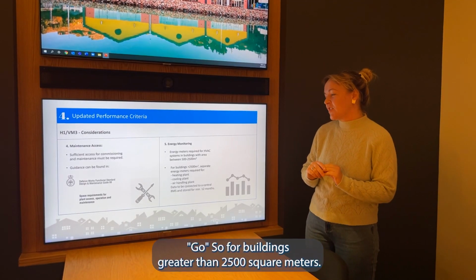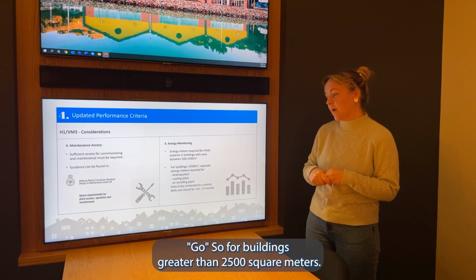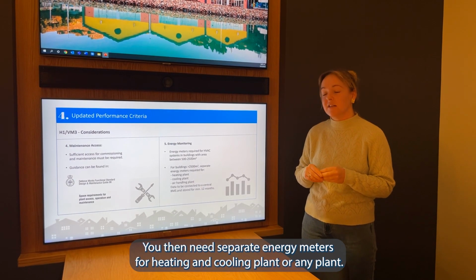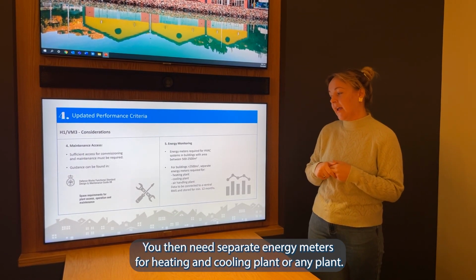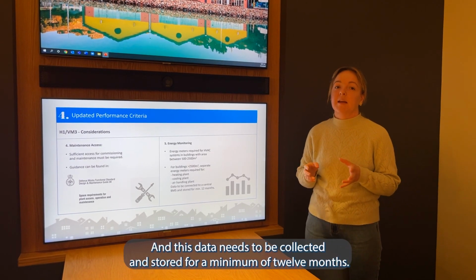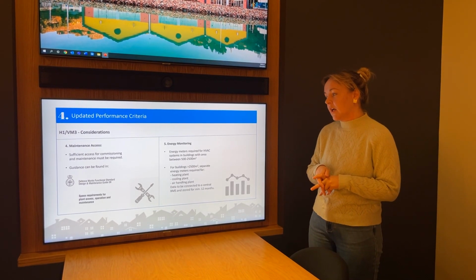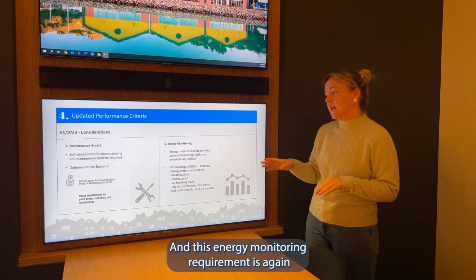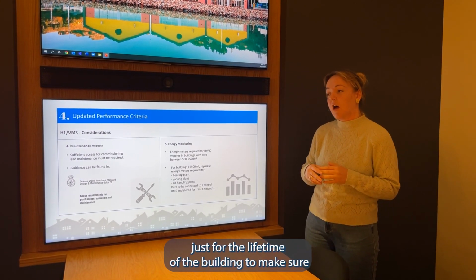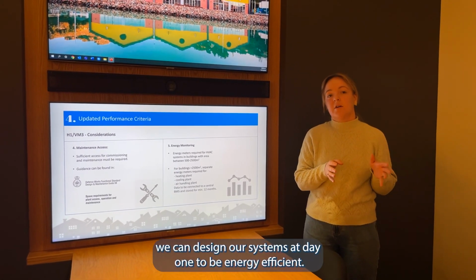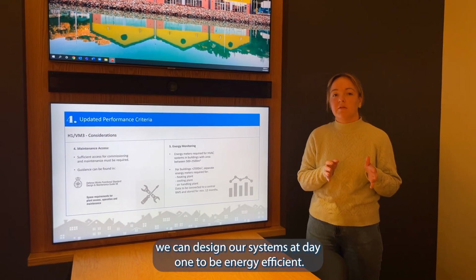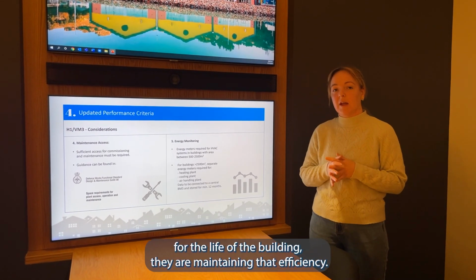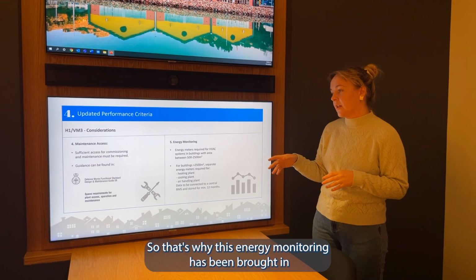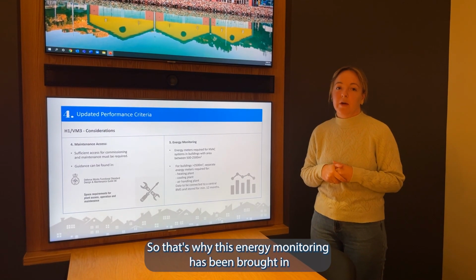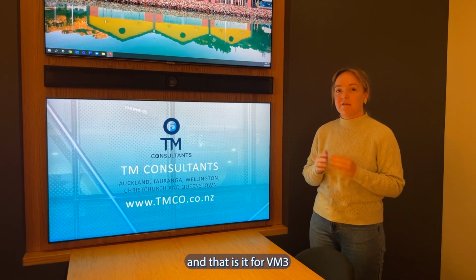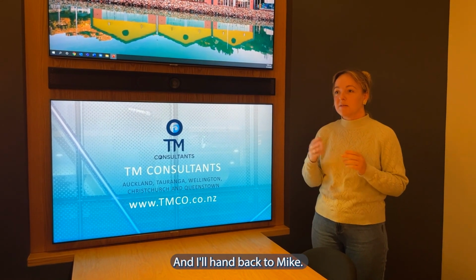So for buildings greater than 2500 square metres, you need separate energy meters for heating plant, cooling plant and air handling plant. And this data needs to be collected and stored for a minimum of 12 months. This energy monitoring requirement is again just for the lifetime of the building, to make sure we can design our systems at day one to be energy efficient, but that then through the life of the building they are maintaining that efficiency. So that's why this energy monitoring has been brought in. And that is it for VM3, and I'll hand back to Mike.